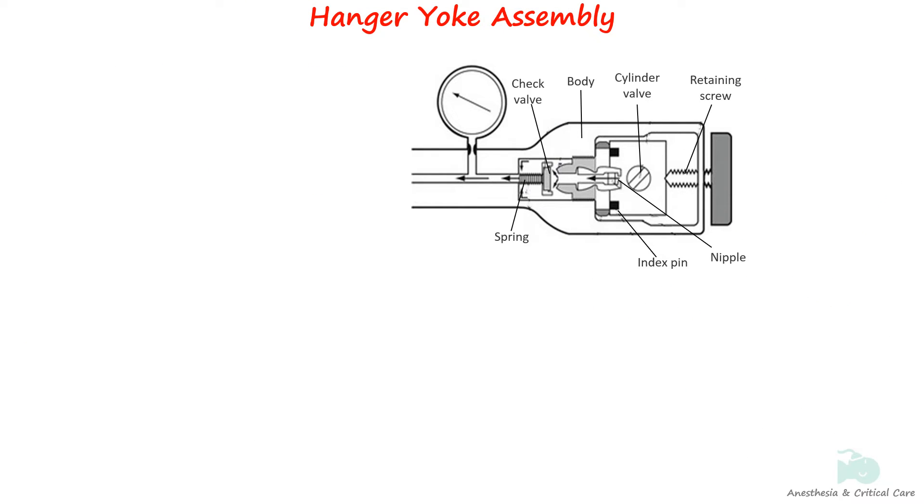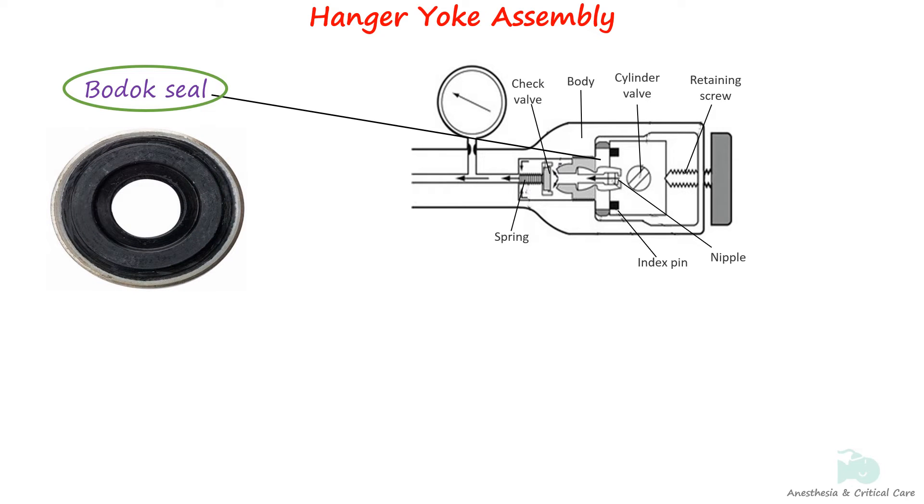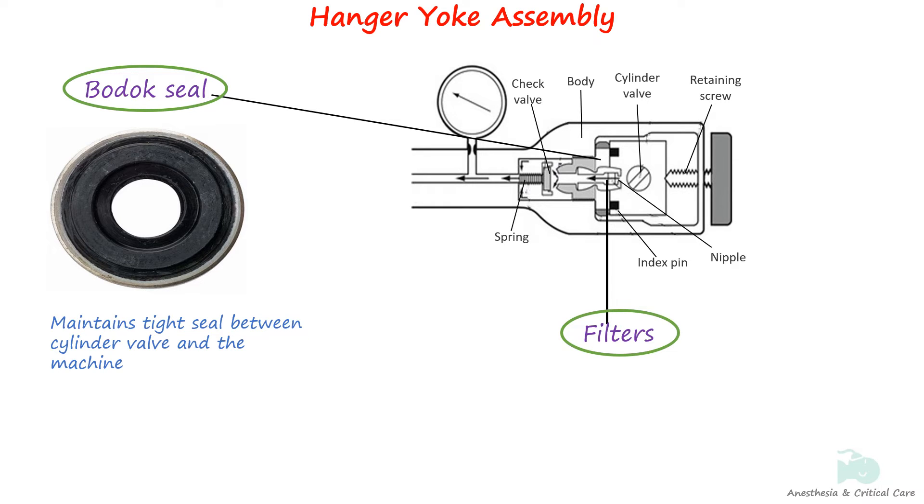The leak-free fitting between machine and the cylinder is achieved by the use of a sealing washer called the Bodok seal. It is made up of non-combustible material with a metal periphery to protect its edges. Only one washer should be used between the yoke and the valve of the cylinder. Filters are placed between the cylinder and the pressure reducing valves to prevent particulate matter from entering the machines.